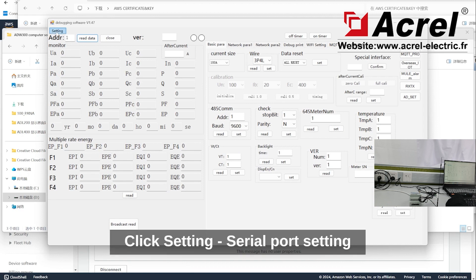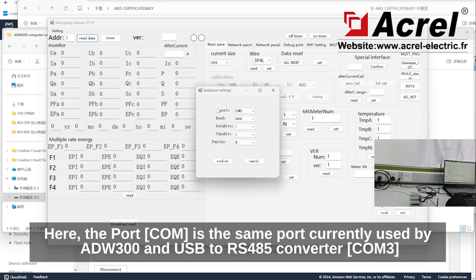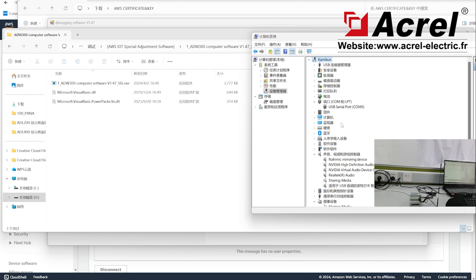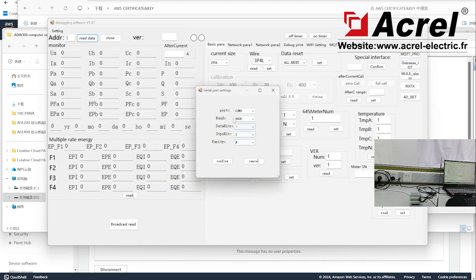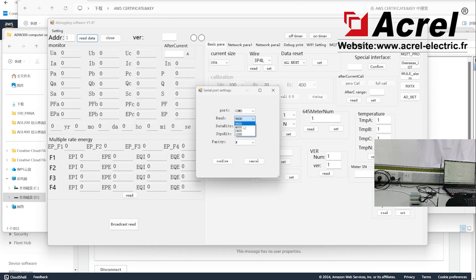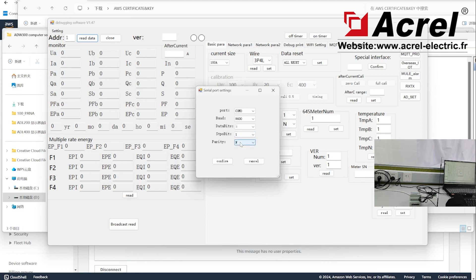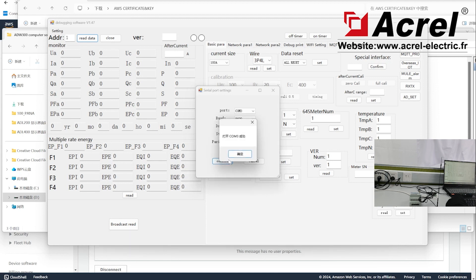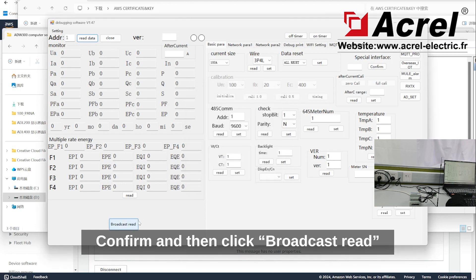Click setting, then serial port setting. The port COM should match the port currently used by your USB to RS-485 converter. Baud rate is default as 9600, data bit is default as 8, stop bit is default as 1. Confirm and then click broadcast read.